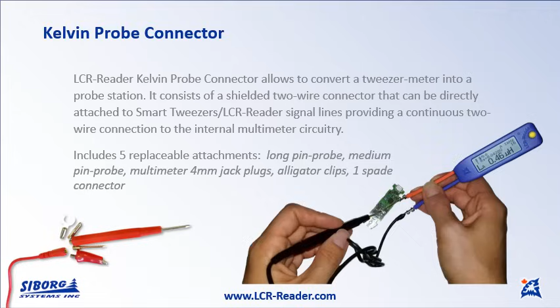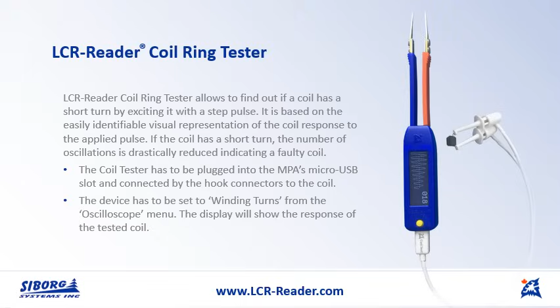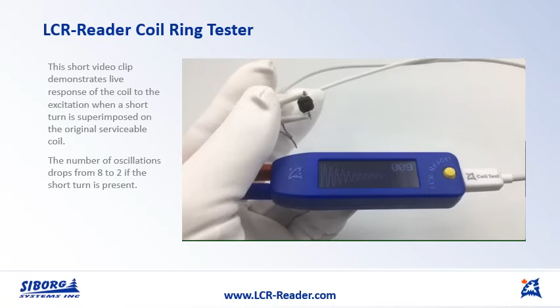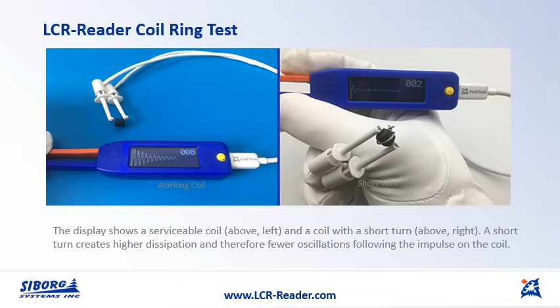LCR-Reader coil ring tester. That one shows the quality of the coil, and it detects if the coil has a short turn around it or within it. This particular slide shows you how the short turn affects the response of the coil tester. You can see that it changes from 8 to 2 oscillations when you introduce the short turn. And here is a picture comparing the two different situations: no short turn and short turn.